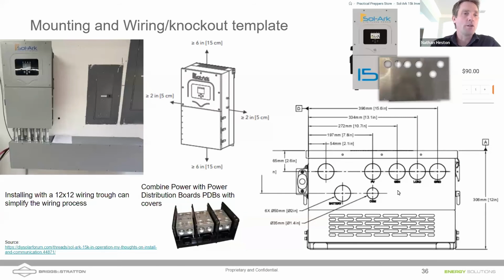Just highlighting here, when you're installing the 15K, if you haven't done it before, using a 12 by 12 wireway gives you a number of options to do different things, such as using power distribution boards inside that wireway to act as combiners. You do need to have at least 6 inches of space below the 15K. The fans are right down there at the bottom, at the same height as the bottom of the electrical panel for the connection. So you've got to have 6 inches of space there.